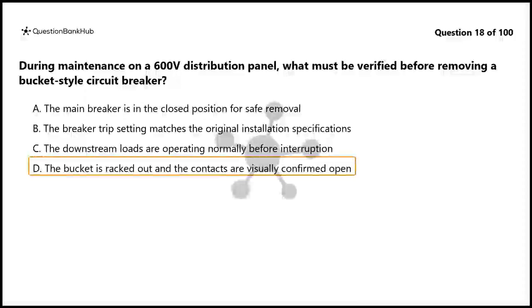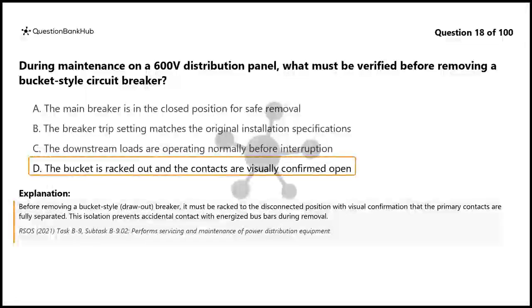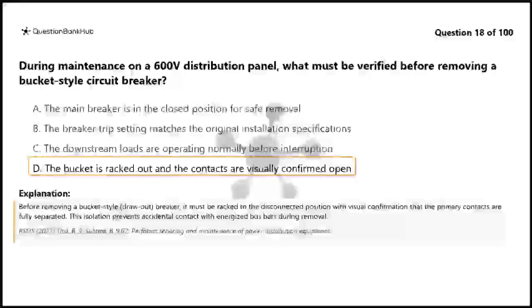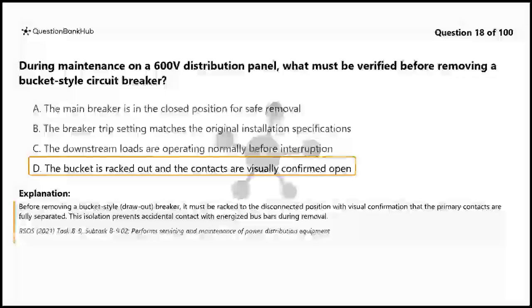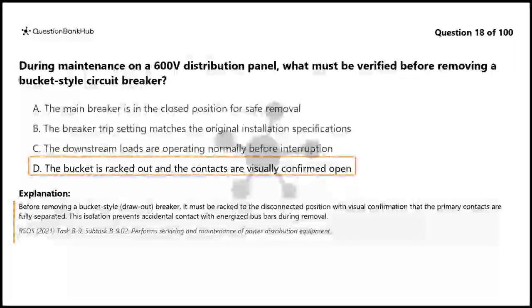The correct answer is D. The bucket is racked out and the contacts are visually confirmed open. Before removing a bucket-style, draw-out breaker, it must be racked to the disconnected position with visual confirmation that the primary contacts are fully separated. This isolation prevents accidental contact with energized bus bars during removal.